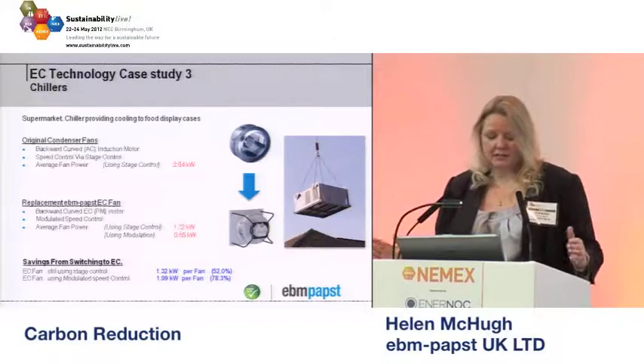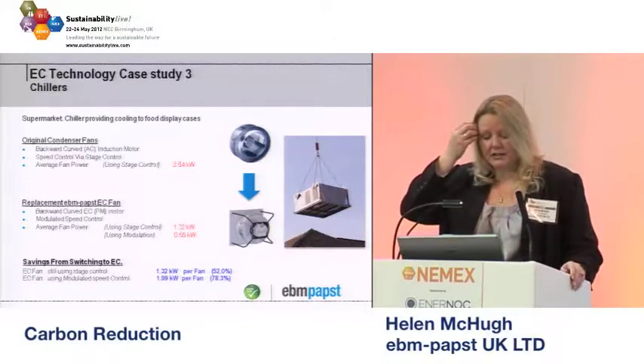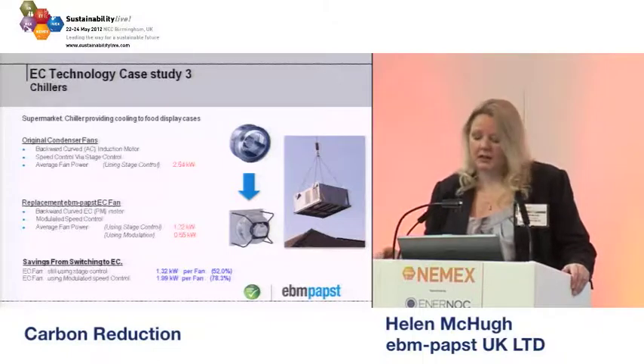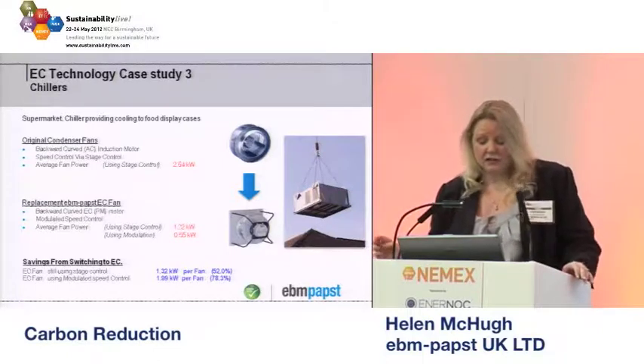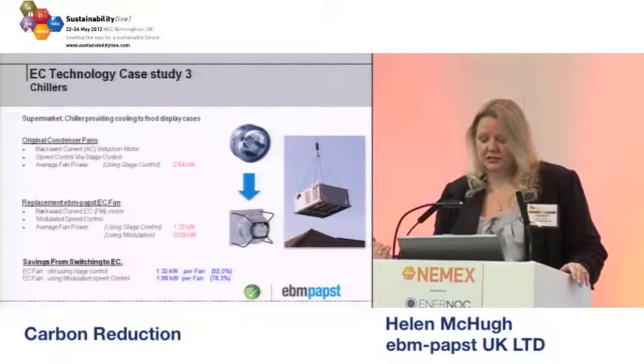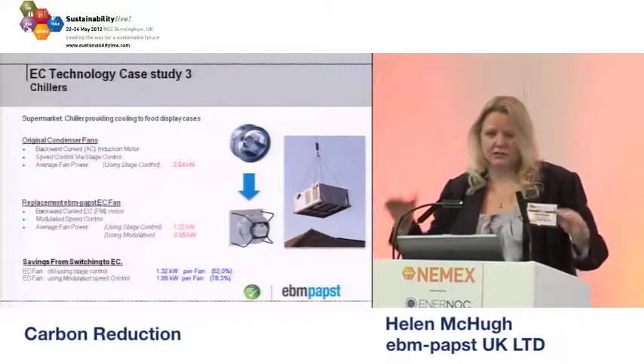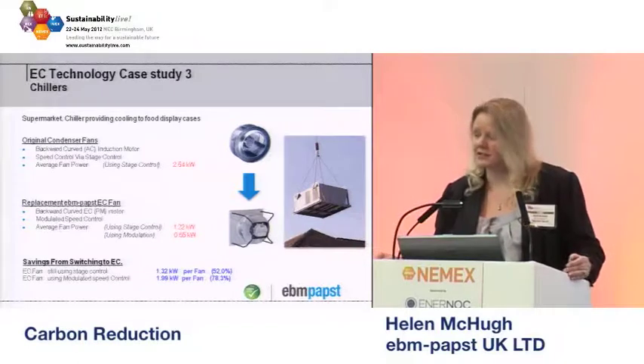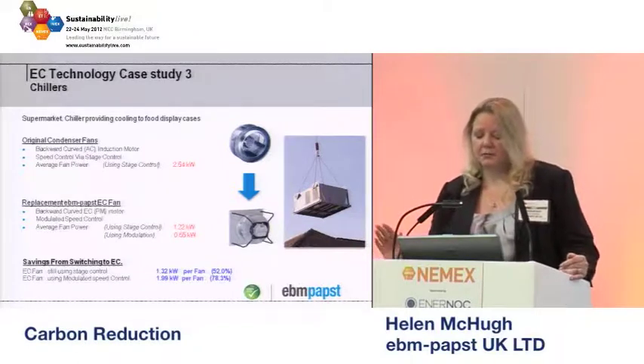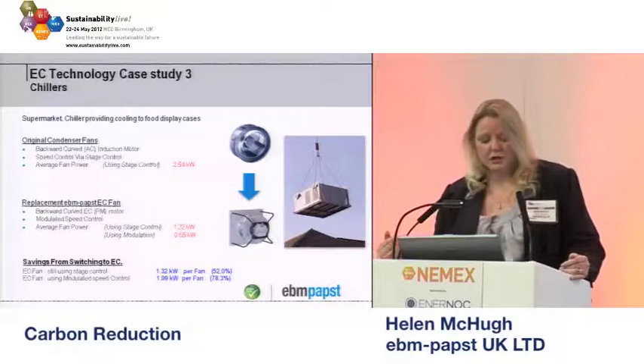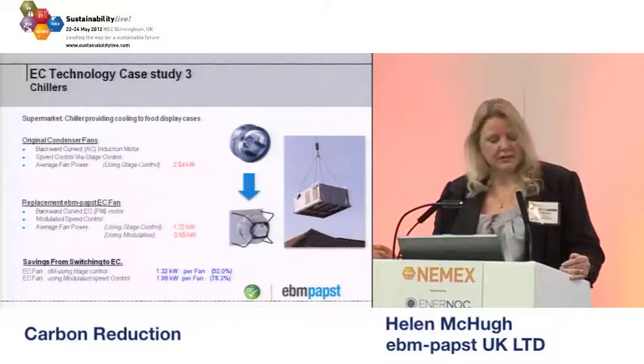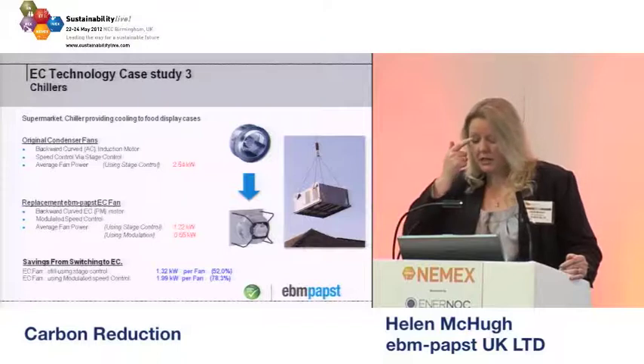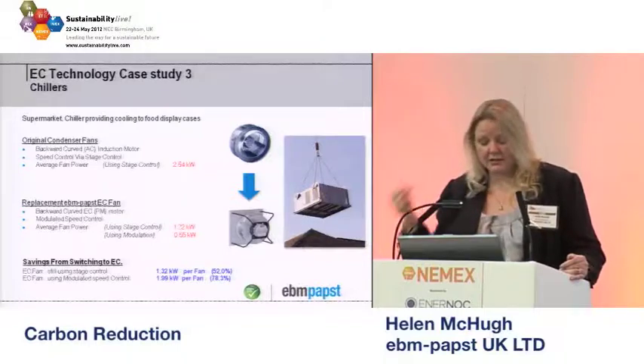Another one is looking at a chiller application. In this case, it's a supermarket. I think this is Iceland. Now, normally you would have axial fans on your chillers. Iceland are actually using a backward curve fan in this case because they're reusing the heat to circulate into their office space. Similar to the last example, we replaced with our EC backward curved fan, and you can see there again an initial saving of around about 50%.